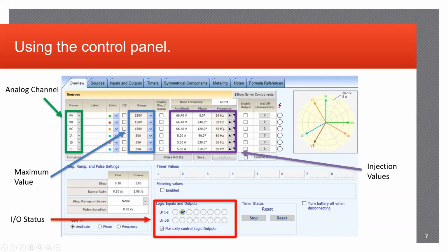This purple square over here is going to be your injection values. It goes into the amplitude and phase, as well as frequencies for your currents and voltages. Again, as we discussed earlier, 66.4 would be your nominal voltage based on the PT ratios as well as the relay settings. Your nominal current ranges can differentiate based on what the relay is going to be looking at, what the settings engineer implemented for the basis, as well as the phase angles for certain testing elements to be picked up and show differentiation on your chart over here.